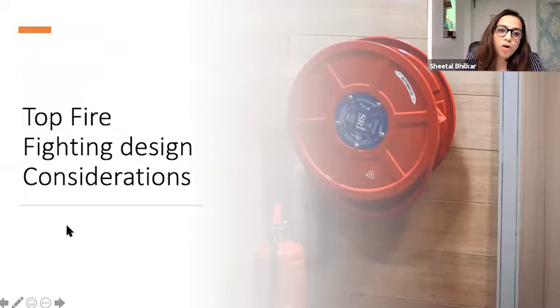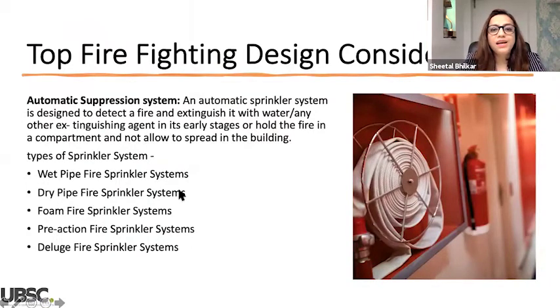Okay, now I'm going to talk about the most crucial, that is firefighting design considerations. So, of course, we design automatic sprinkler systems to detect fire and extinguish with water or extinguishing agents at early stages, so that the fire is held in the compartment and not allowed to spread in the building. So types of sprinkler, as we all know, wet type sprinklers, dry type sprinklers, foam fire sprinkler system, pre-action, deluge, all the sprinkler systems we use.